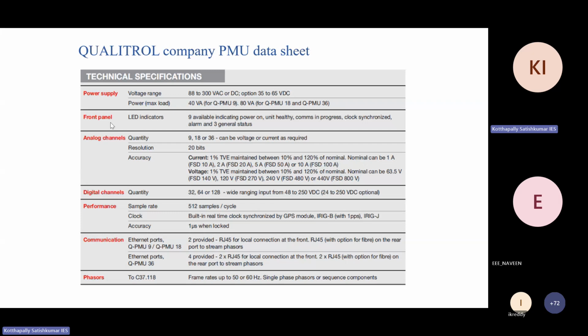Now here, on the front panel, they will have LED indicators which show whether the unit is healthy, whether communication is in progress, and whether the clock is synchronized. So you can see these LED indicators. They tell the status of the PMU. Using these signals you can understand whether communication is working, because physically you cannot tell whether communication is going on or whether the clock is synchronized or not. So they gave these LED indicators, which tell whether the clock is synchronized, whether the unit is healthy, and whether communication is in progress or not.